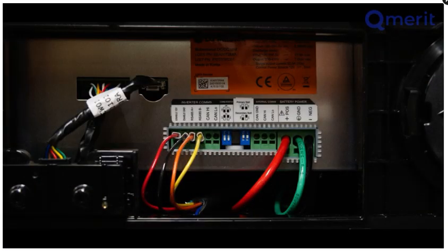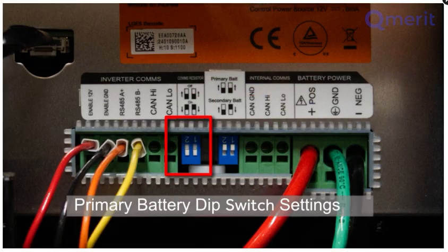Dip switch settings for primary and secondary packs. When connecting a single battery pack, use the primary switch settings. Since this is a primary battery pack, we will set the 2 dip switches on the left to the down position. The 2 dip switches on the right will be set to the up position.